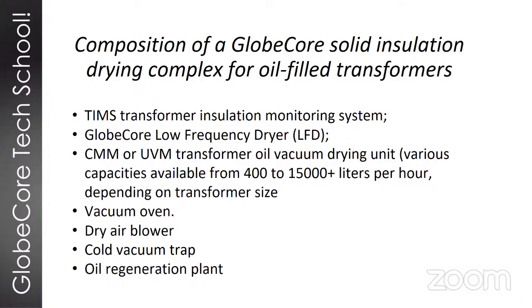All of these machines have different processing rates that can vary from 400 to 15,000 liters per hour. They can also be used in combination with a vacuum oven, a hot air blower, a cold trap, and of course an oil regeneration plant. In the next few slides, we're going to look at some of the more typical combinations of equipment for drying of insulation. If we can go to the next slide.